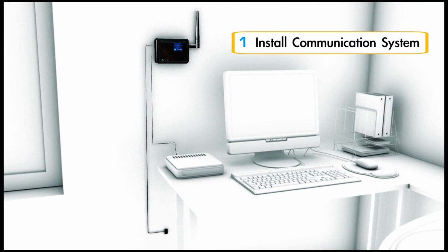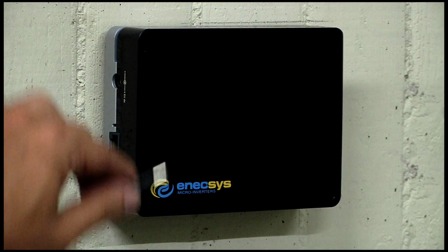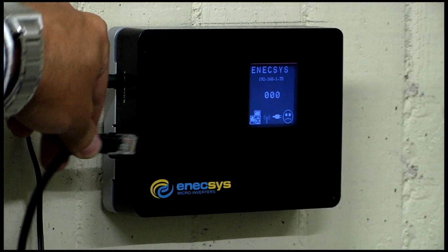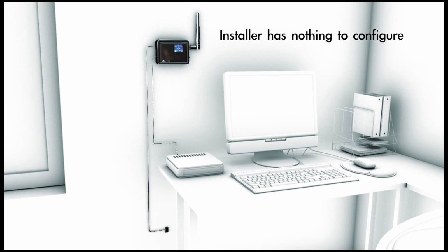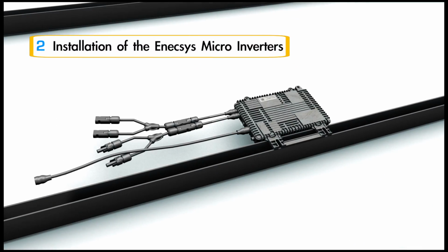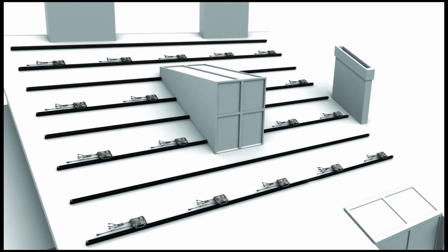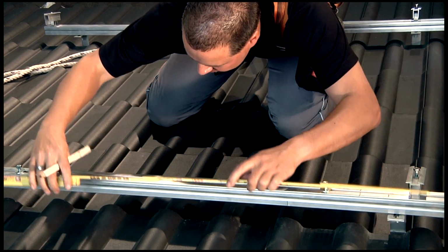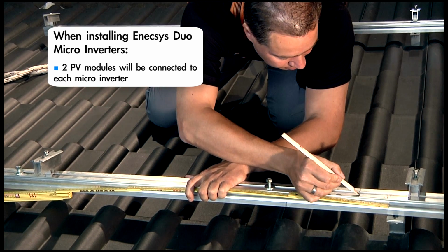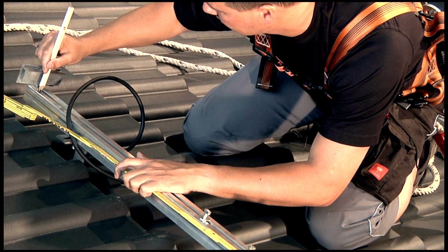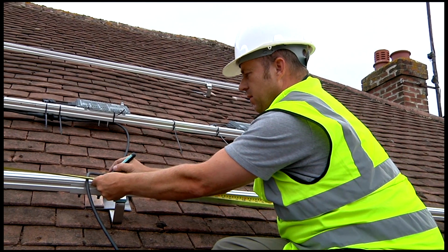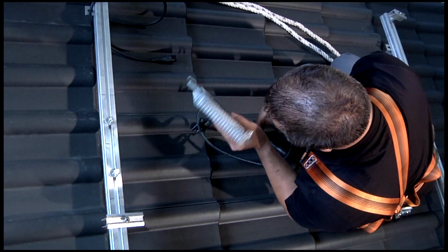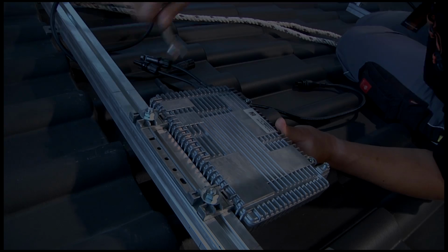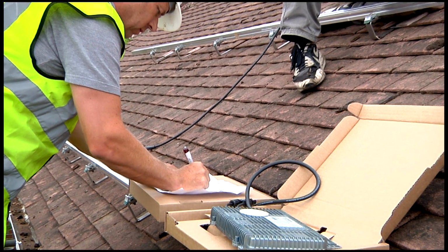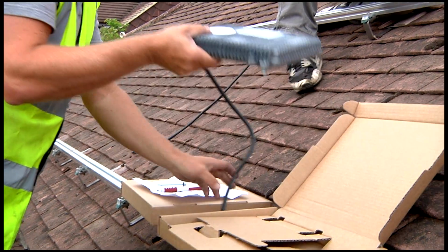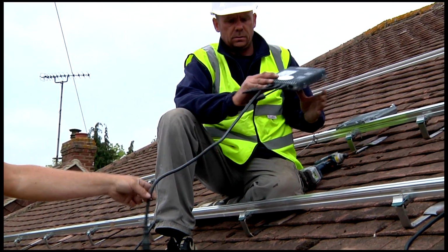Step 1. Install the communication system. Connect the gateway by simply plugging it into an internet router using the provided Ethernet cable. That's it. On to step 2, installation of the Enecsys microinverters. Mark the approximate center of PV modules where the microinverter is to be installed. And note, when installing Enecsys dual microinverters, two PV modules will be attached to each microinverter. Position the microinverter with the product label facing the roof and mount the microinverter on the railing system. Be sure to record the serial number and position of each microinverter for reference purposes.